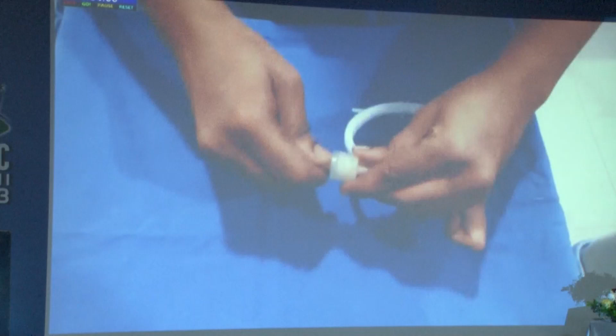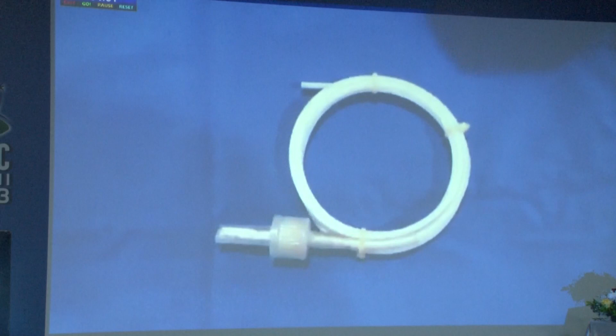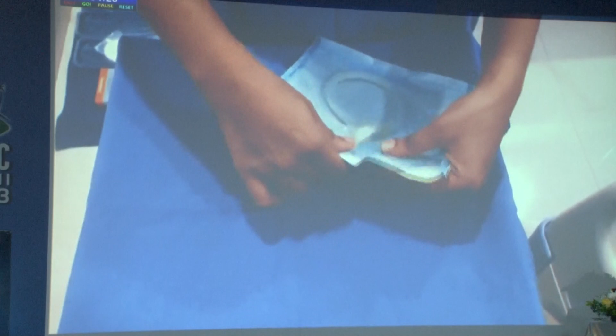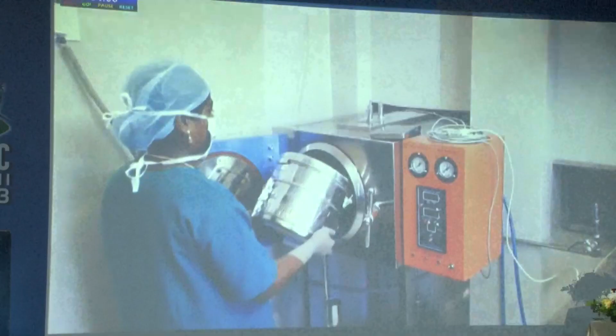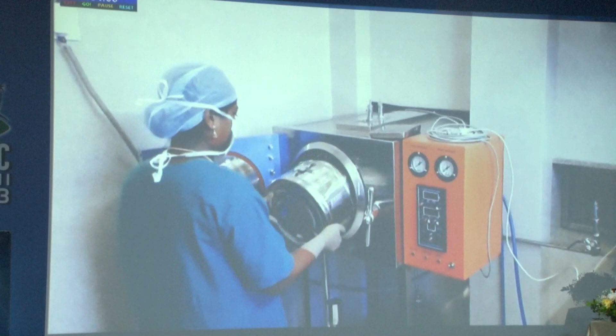This is simply based on the principle that your autoclave should be efficient enough to remove the air first, and then has the adequate pressure to push the steam inside this series of tube to reach the indicator on the other side. Again, pack it exactly the same way as you pack your phaco set and the other instruments. And then place it exactly the same way you place your instrument. So you're actually simulating exactly the same demanding technique for your instruments also. And then it is packed inside an autoclave.